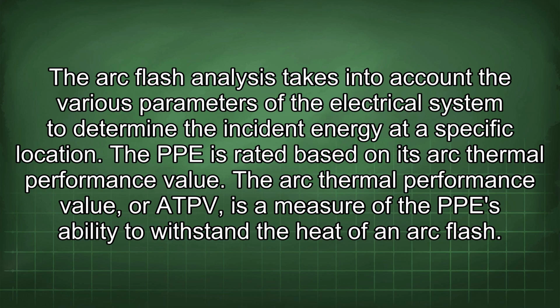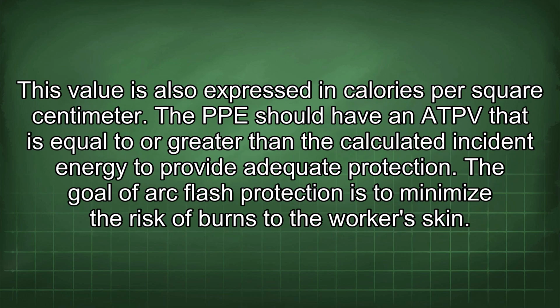The PPE is rated based on its arc thermal performance value. The arc thermal performance value, or ATPV, is a measure of the PPE's ability to withstand the heat of an arc flash. This value is also expressed in calories per square centimeter. The PPE should have an ATPV that is equal to or greater than the calculated incident energy to provide adequate protection.